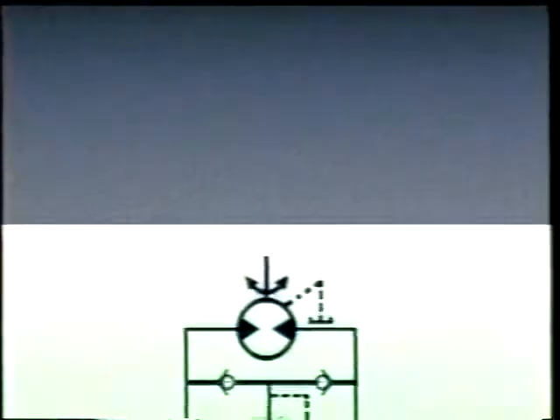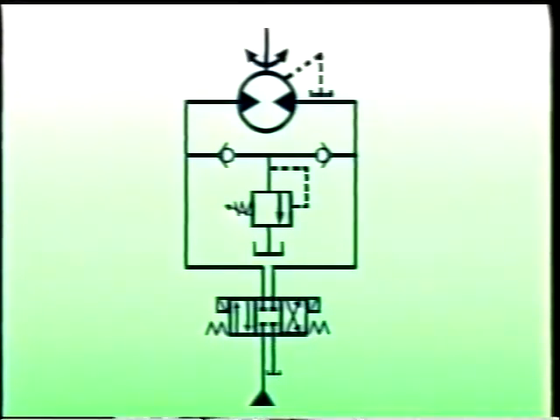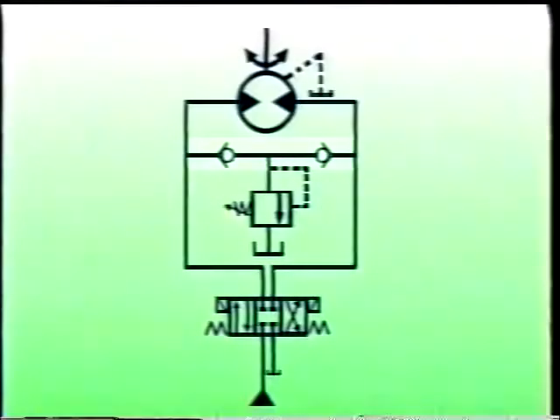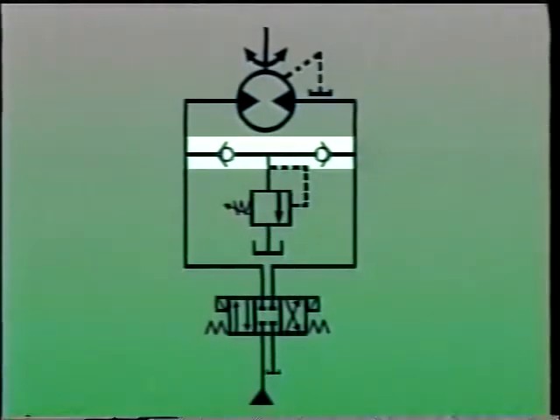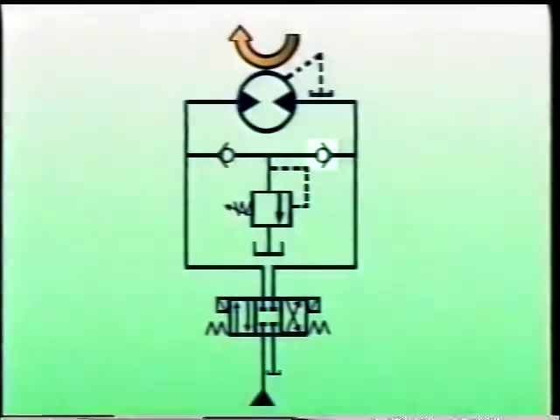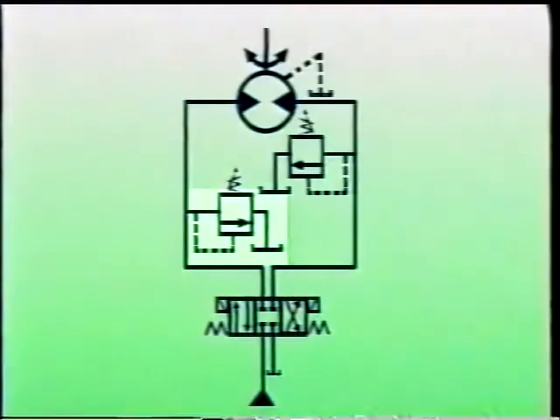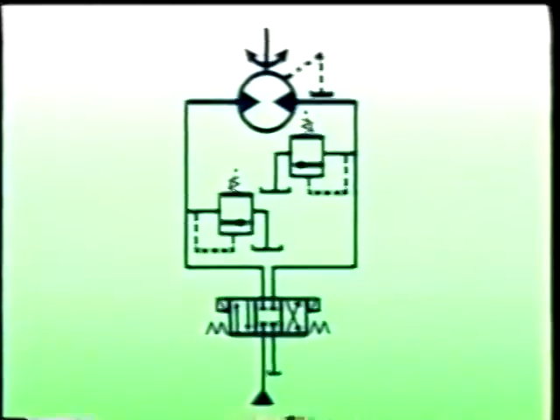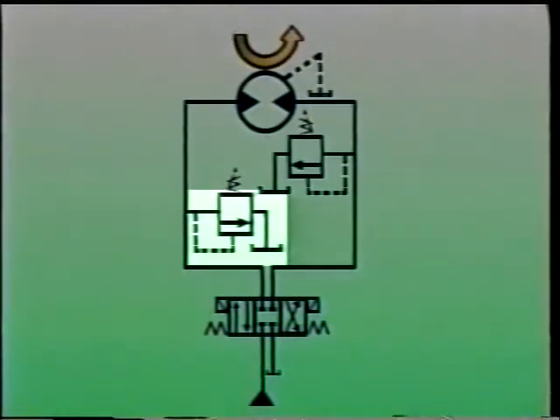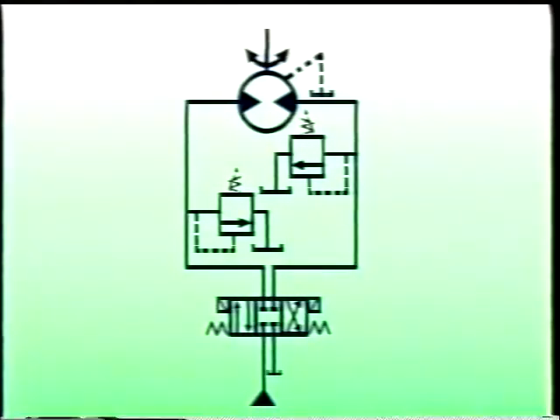Bi-directional motors — motors that can rotate in either direction — can be braked in a similar way. In this circuit, the same relief valve can be used even though the motor can be braked in either direction, because dual check valves isolate the braking side of the circuit no matter which direction the motor is turning. The check valve on the left prevents fluid from returning to the left side when the motor is braked while turning clockwise, and the check valve on the right prevents fluid from returning to the right side when the motor is braked while turning counterclockwise. When two different loads must be braked, two relief valves may be used to apply two different braking pressures — one limits braking pressure in one direction, and the other in the other direction.